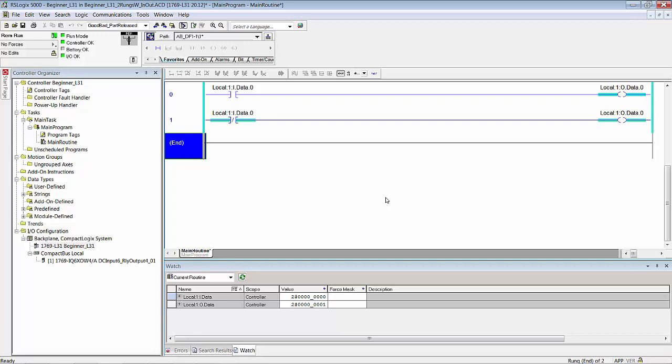With RS Logix 5000, and remember that the rev level of the controller has to match the rev level of the software, the app that you're using, what you're looking at right here. They have to be the same. That has changed, for the most part, every 9 months since its inception. That's kind of a rabbit that you have to chase continually with the Logix platform. It's not a big deal once you're used to it, and being able to flash the firmware on a processor or an I/O module is very simple. So it's not as convoluted as it sounds. Nonetheless, we have version 20 of 5000 and the controller.